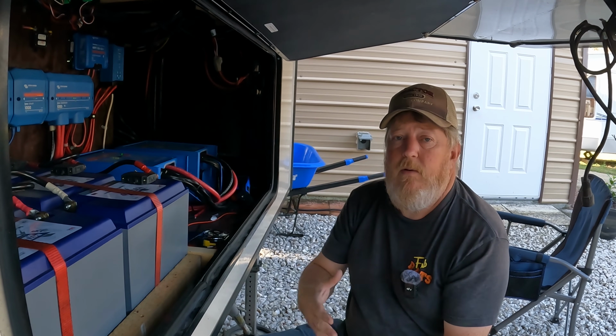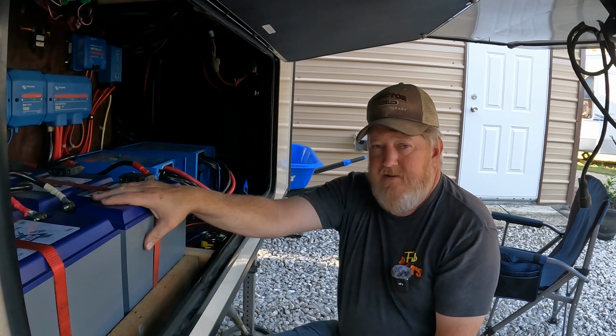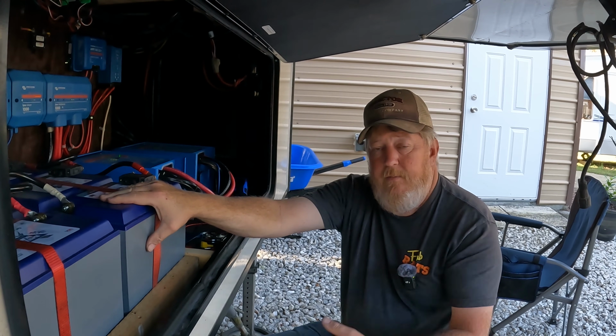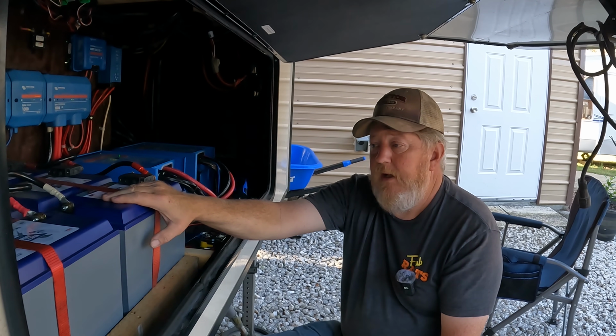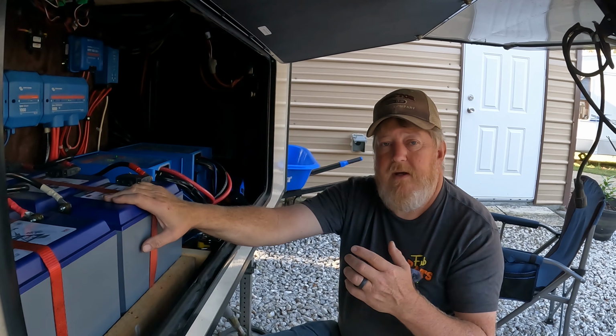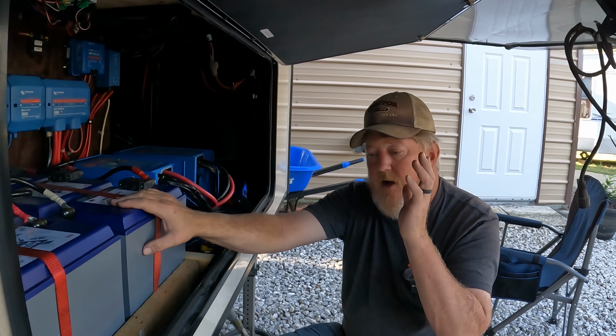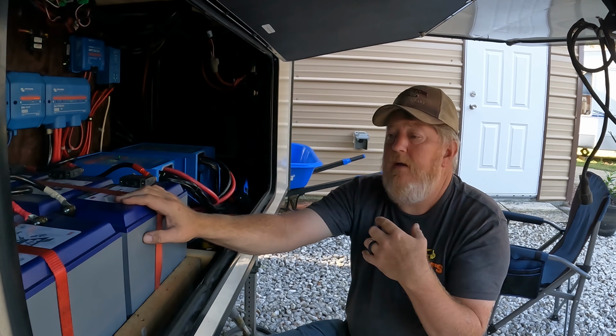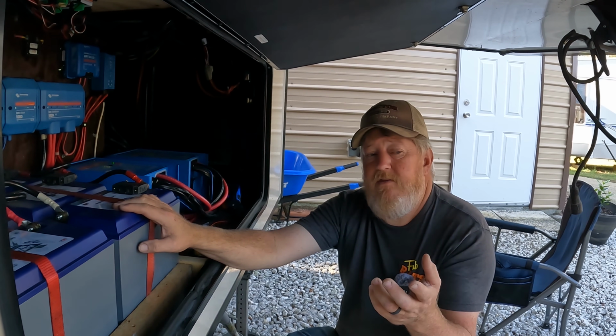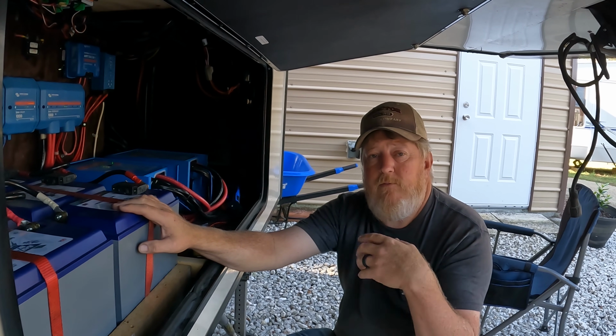One of the things I want to do is run a single string of batteries at 50 amps, which is the Battleborn recommended power level. I'm not going to do it for very long because I already know I'm taking these out. I don't need any convincing on my part. I want to show you what happens when we run those batteries at 50 amps for 10 minutes, and we'll show you the temperature rise.